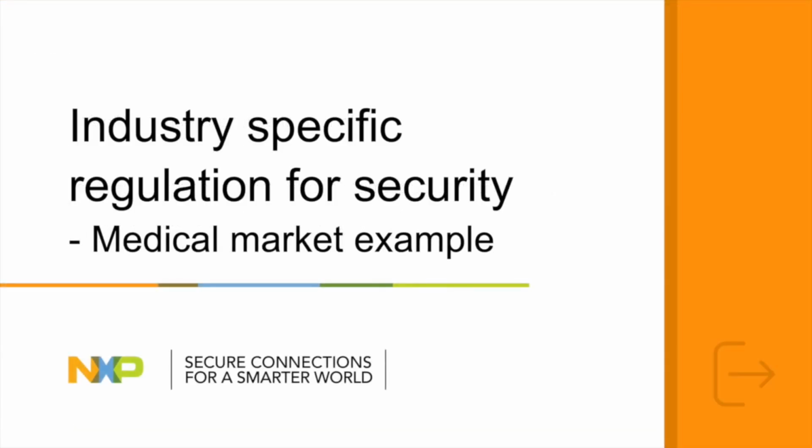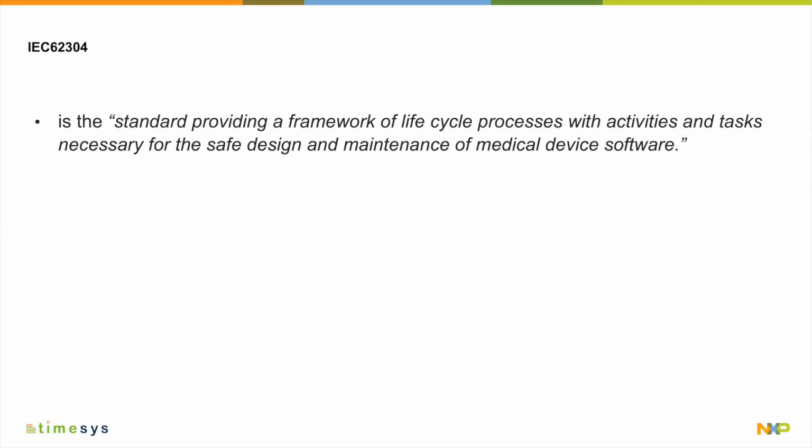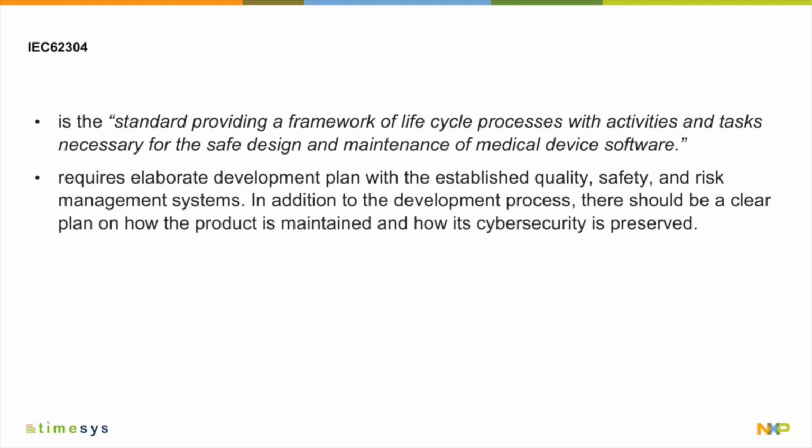Let's talk about industry-specific regulation for security, and I've chosen the medical market as an example here. 62304 is the standard that defines the framework of lifecycle processes with activities and tasks that are necessary for the safe design and maintenance of medical device software. The standard puts the requirement on a company to create a development plan with very well established quality, safety, and risk management systems. There should also be a clear plan to maintain the product for security long term.